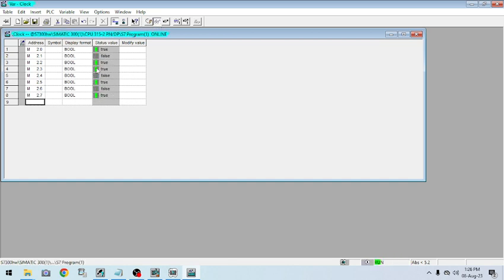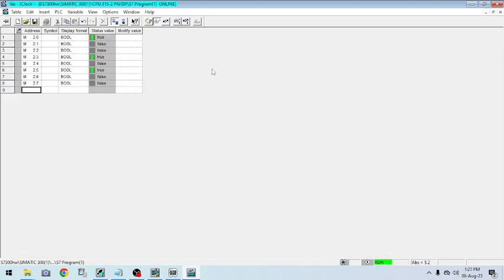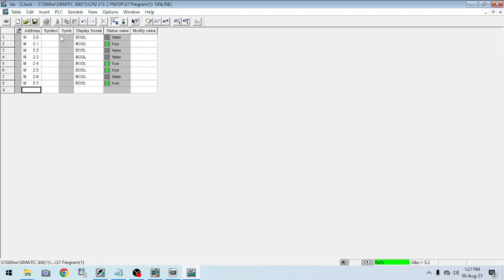Now you can see the eight bits of data are shown here. Going online, you can see my clock bits have started. These clock bits are used for things like horn alarms, audible warnings, flashing lights for alarms, or trip signals. For checking this kind of alarm, we need to give symbols — this is the symbol address. So I can define, for example, Flash 10 Hz.